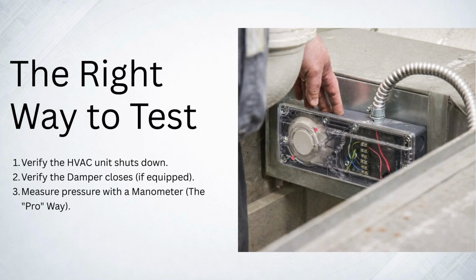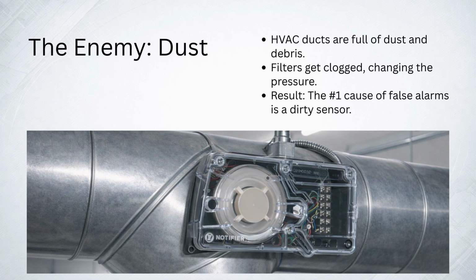So why do they false alarm so much? The answer is simple: dirt. HVAC ducts are the lungs of the building, and they breathe in dust, pollen, and construction debris. Over time, the air filters in the unit get clogged, which changes the pressure in the duct. Furthermore, fine dust bypasses the filters and coats the inside of your smoke detector. When the sensor gets dirty, it becomes hypersensitive. A little bit of humidity or a change in fan speed can trick a dirty sensor into thinking there is a fire.